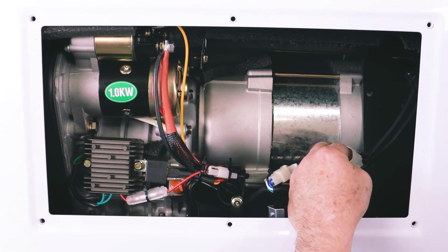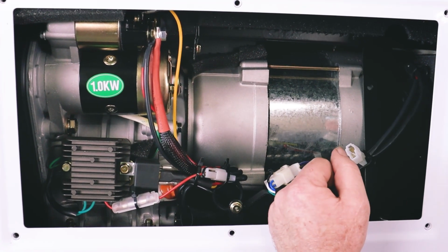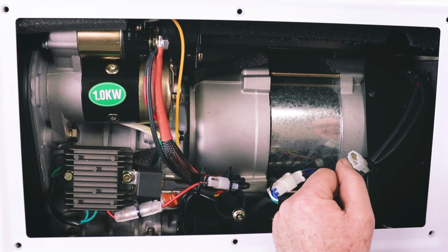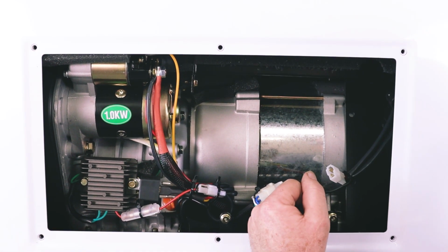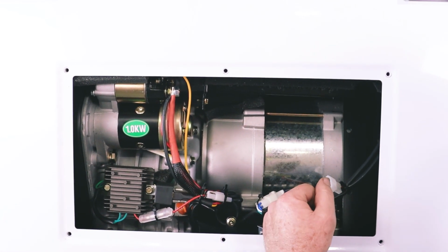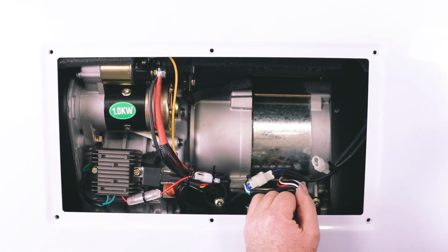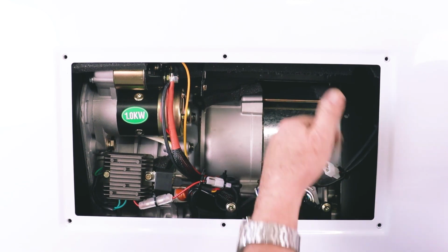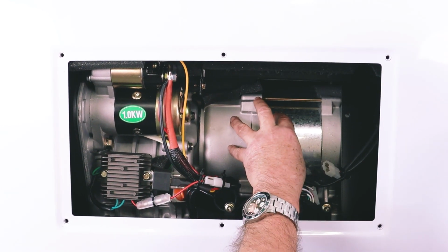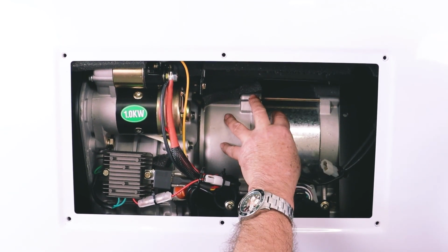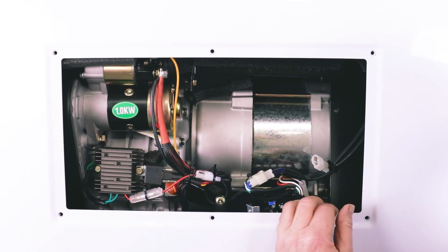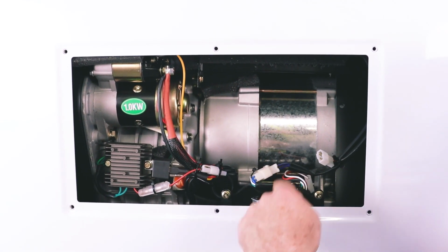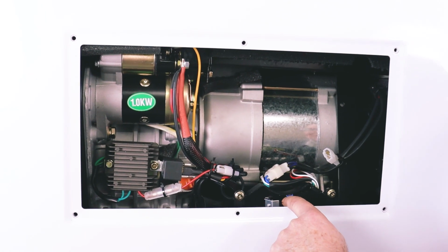What I'm going to do is rule out the AVR by putting 12 volts onto here, so I'm expecting when I start the engine to get a low voltage reading on the clock. Probably somewhere over 100 volts, but nowhere near 230, maybe 140 volts, something like that, when I'm probing on the 230 outlet socket. So we'd see voltage come back, the generator's producing power, but not the correct power, because I'm not supplying the correct DC. That would point us in the direction that the AVR is at fault.